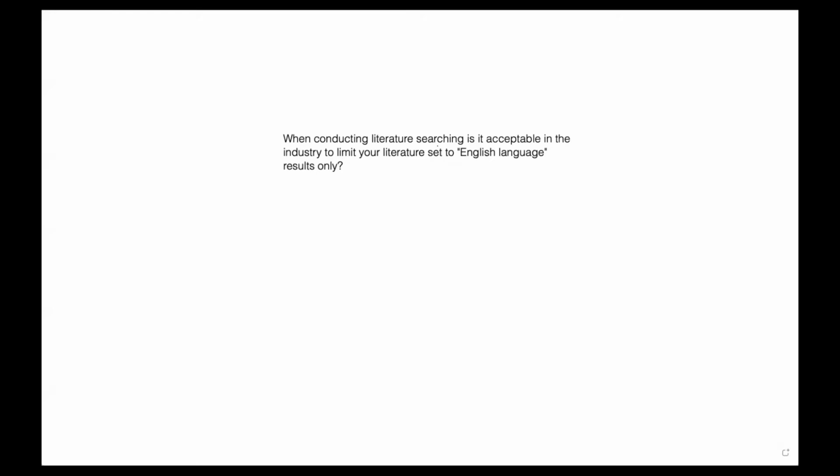We've been at this MDR and CER thing since 2016, and that was a hot topic for a few years. We have found in our experience in the last 2 or 3 years that there's been no pushback whatsoever from a notified body of any of our clients that we set it to English language only. There doesn't seem to be any expectation that a manufacturer would go through the trouble of translating an article on the off chance that it may have additional information.